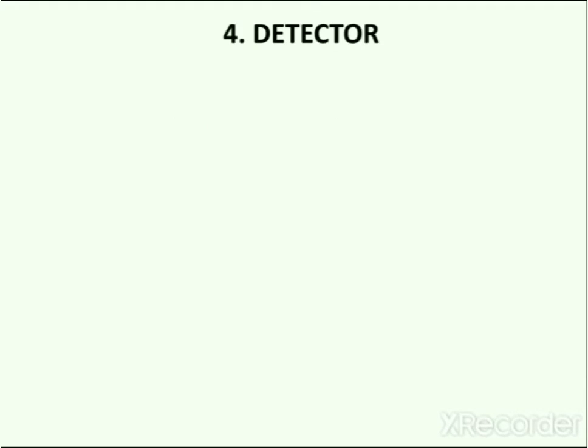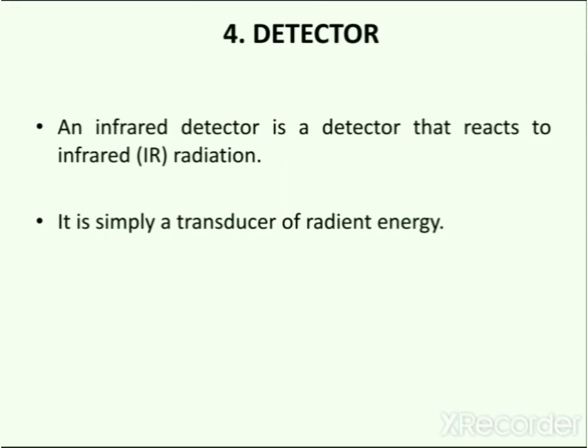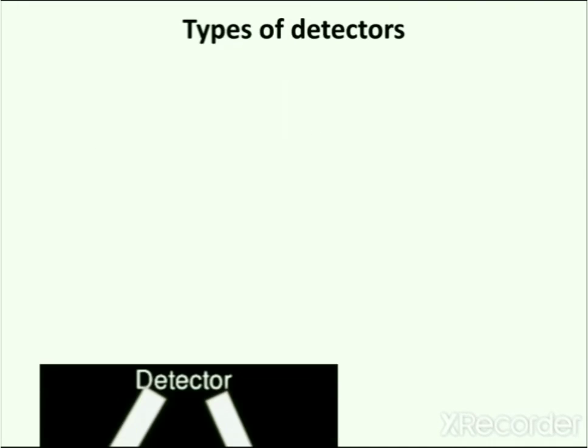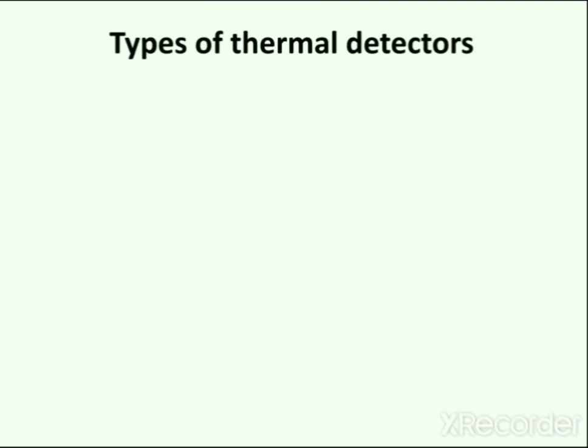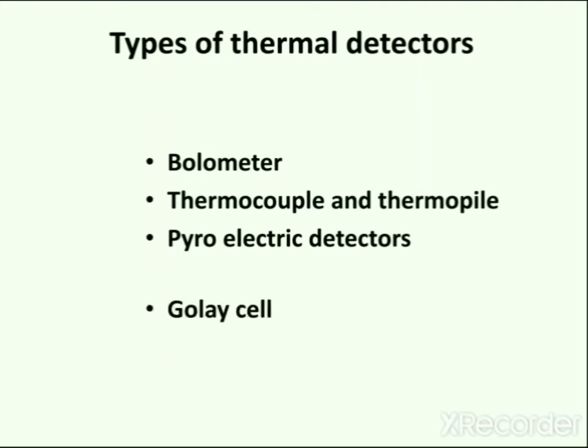The next important part of the IR instrument is the detector. An infrared detector reacts to infrared radiation and is simply a transducer of radiant energy — an electronic device that converts energy from one form to another. There are two types of detectors used in IR spectrophotometers: thermal and non-thermal detectors. Types of thermal detectors include the bolometer, thermocouple and thermopile, pyroelectric detectors, and the Golay cell.